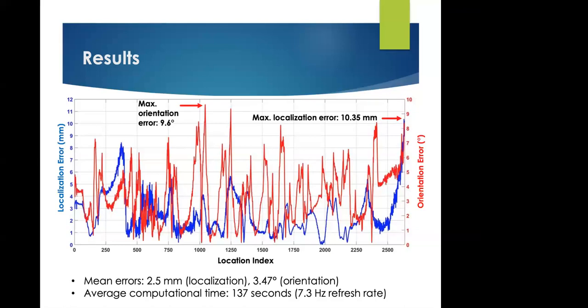Here's another view of the results, where we see that 10 millimeters is the maximum error that we get, at only one location, but on average we get about 2.5 millimeter localization error and about 3.5 degrees for the orientation error. What's even more important is the average computational time, which currently stands at about 137 milliseconds. There are ways, of course, to optimize that even further. This gives rise to about a 7 Hertz refresh rate, so we can calculate about 7 location estimates every second, which can be considered acceptable for the real-time requirements for RCE, considering that we don't expect the capsule to move very fast inside the body.